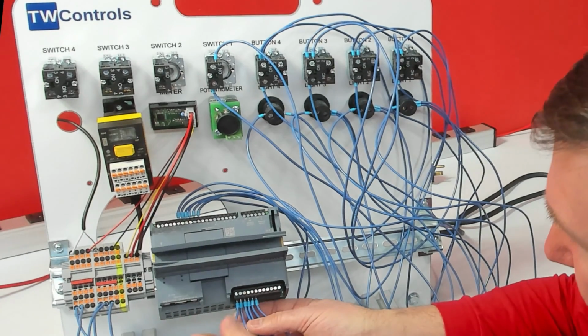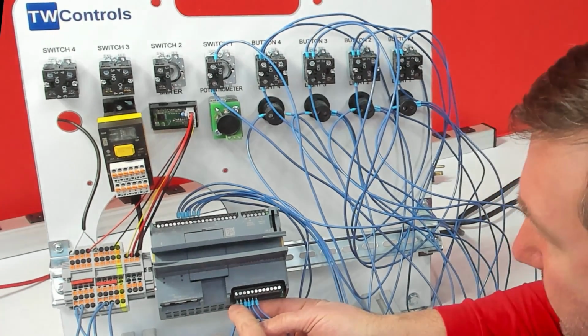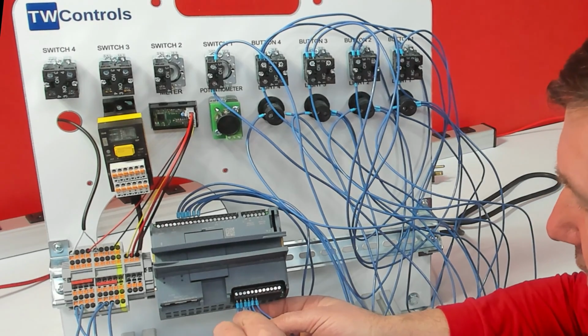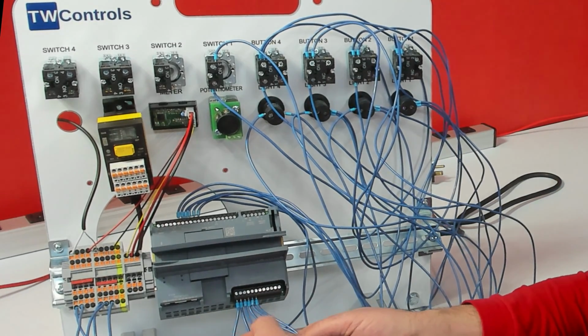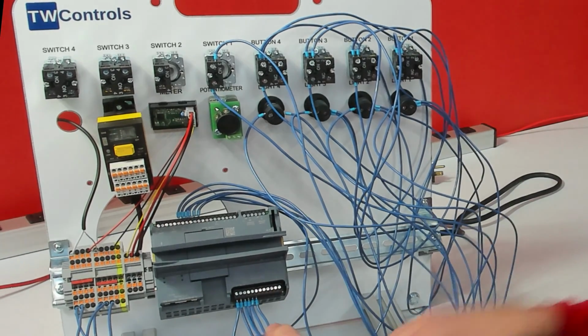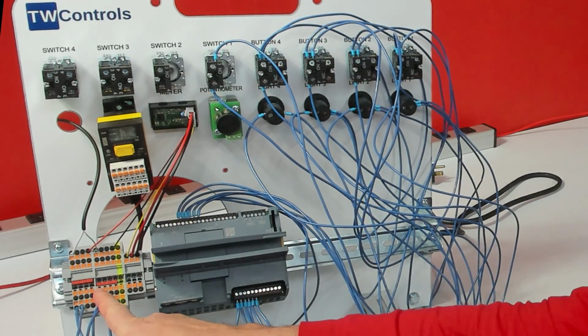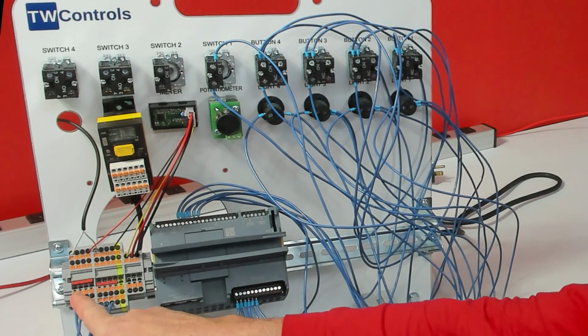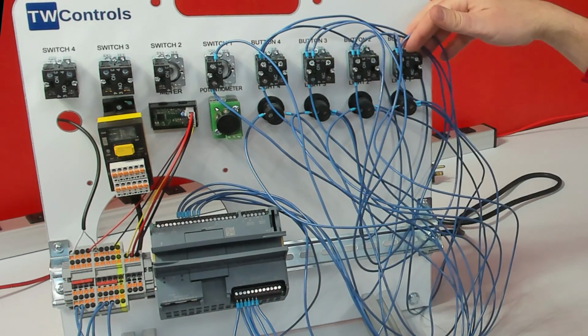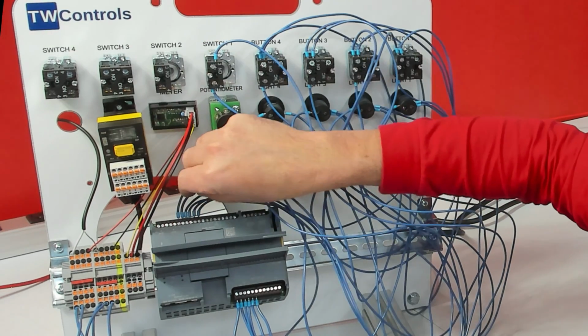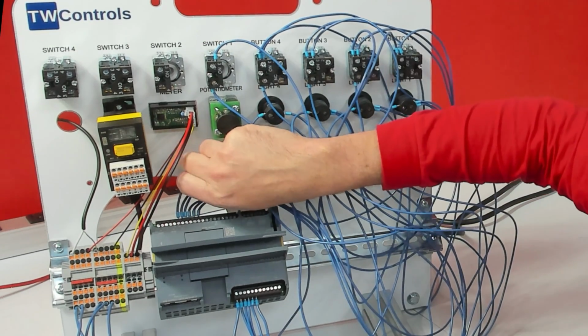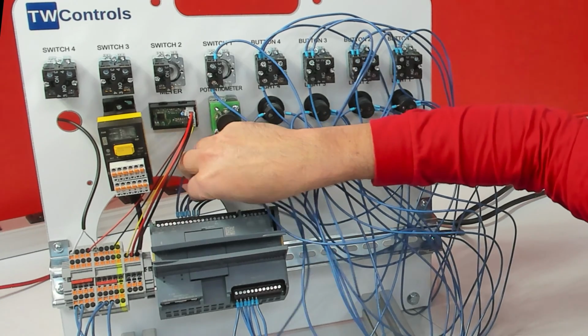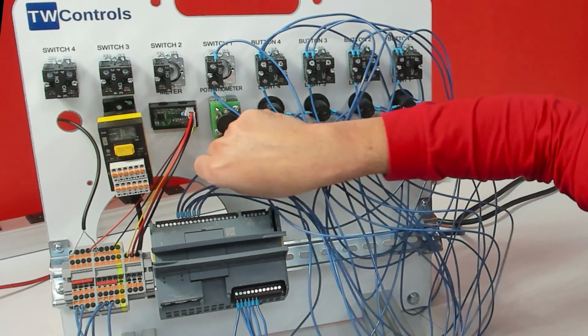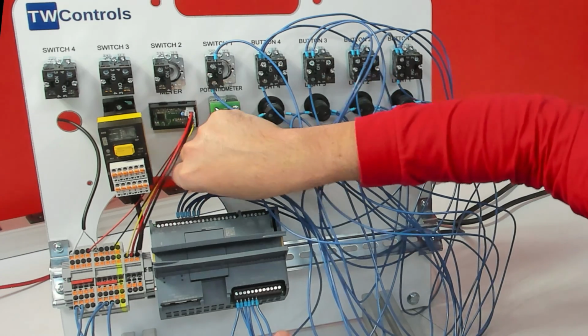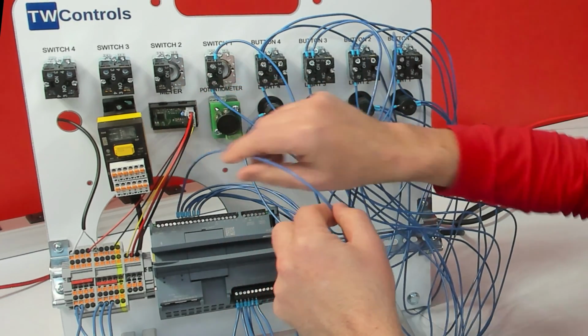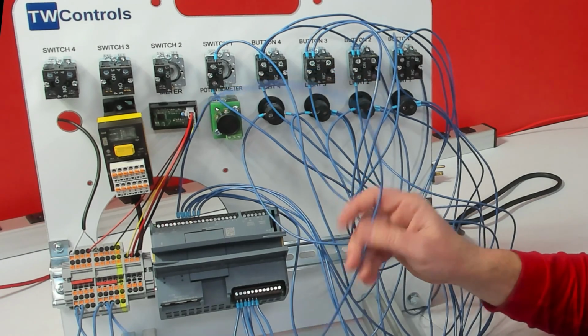So quick review, you should have plus 24 on the 4L plus terminal here, the 4M's minus 24, then light 1, light 2, light 3, and light 4. The opposite side of those go to the minus of the power supply. And we're feeding 24 volt to the top of all of our buttons and switch 1. Then we're taking button 1 to input 0, button 2 to input 1, button 3 to input 2, button 4 to input 3, and switch 1 to input 4. And again, the most often overlooked wire is this M right here goes to the minus of our power supply.